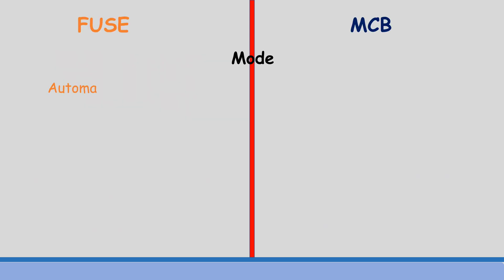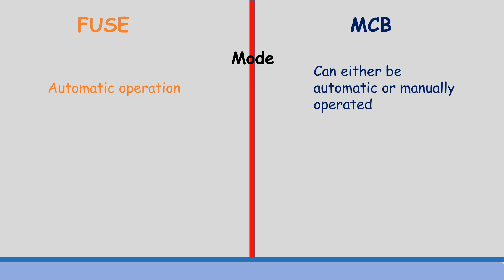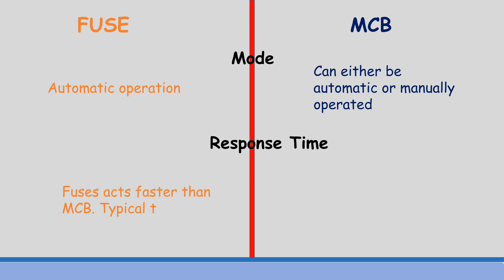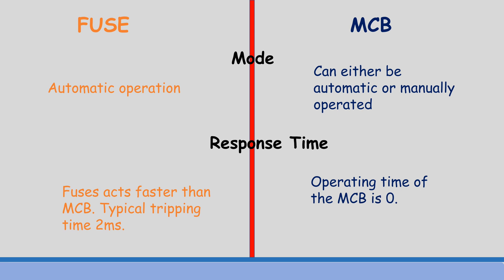The function of a fuse is automatically operated. MCBs can either be automatic or manually operated. Fuses act faster than MCBs, with a typical tripping time of 2 milliseconds. The operating time of the MCB is 0.02 to 0.05 seconds.